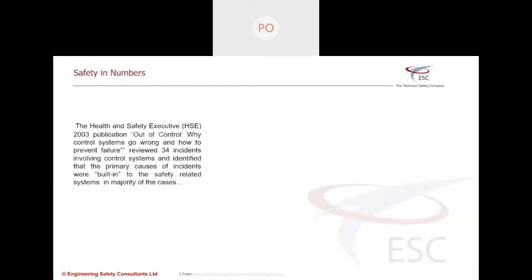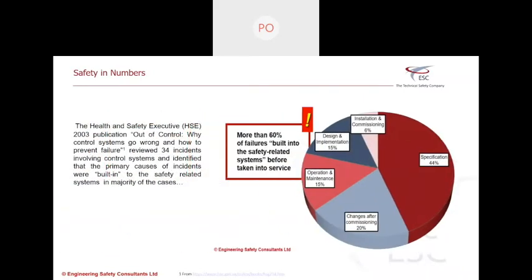Some of you are going to be familiar with what this slide is going to show. Some of you won't. In both cases, I think it's valuable that we have a bit of time to discuss this. In 2003, the health and safety executive conducted a research on incidents associated with control systems. And they identified that the primary causes of incidents were built into the safety systems in the majority of the cases. If you have a bit of pen and paper, just note down the number of causes that were in built, a percentage, and what you thought was the major cause. You might be surprised, you might not. What was found in that research was that more than 60% of the failures were there before you use them.